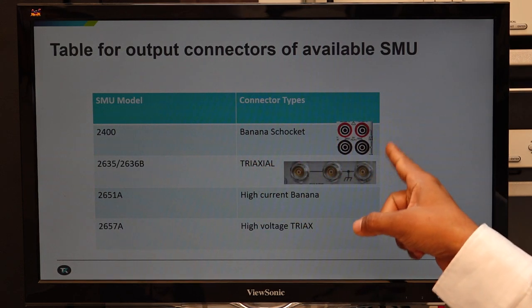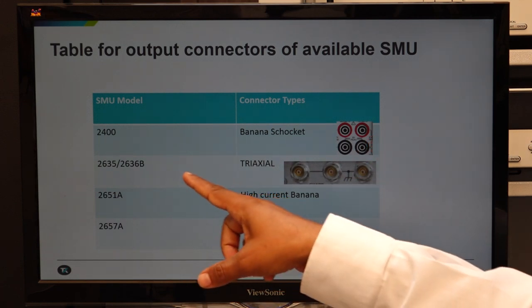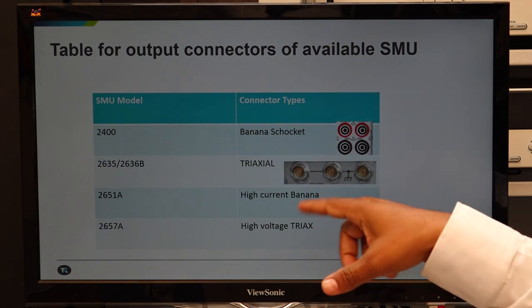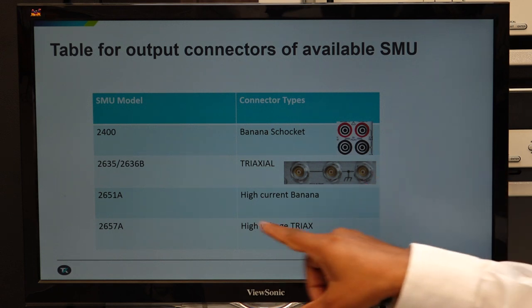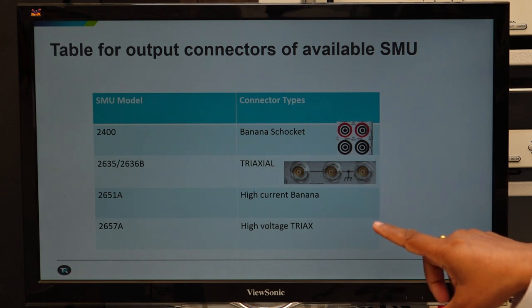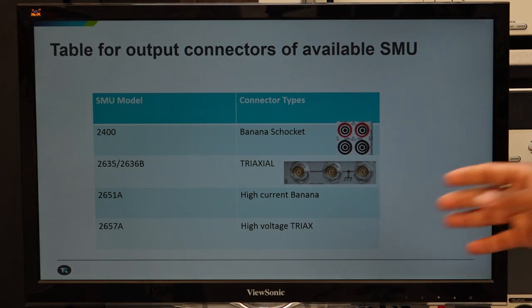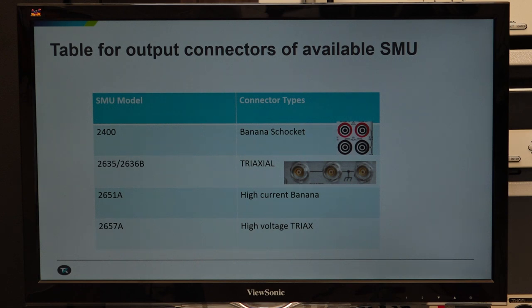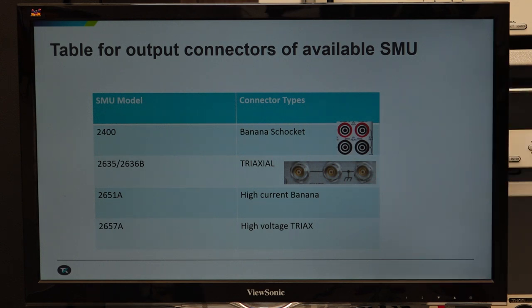All four types of SMU have different connectors. The 2400 comes with standard banana sockets. The 2635 and 2636, being low current SMUs, come with built-in triax connectors. The 2651 again uses banana but high current banana sockets. The 2657 comes with high voltage triax. These connectors differ in electrical properties and mechanical specifications. When using these SMUs in setups with probe stations or chambers, connections to the final device must ensure no unnecessary noise or discontinuity during measurement.